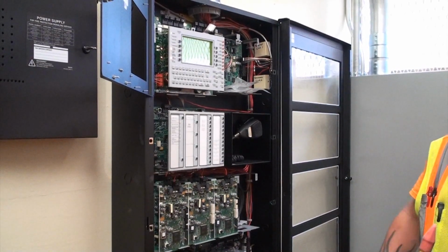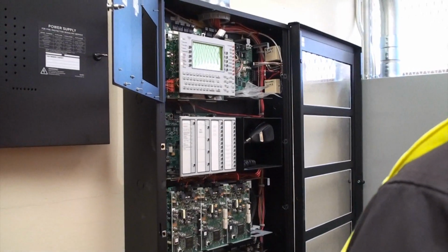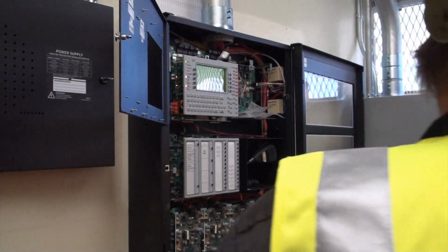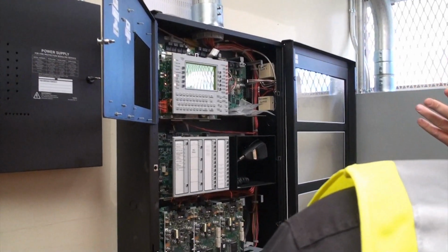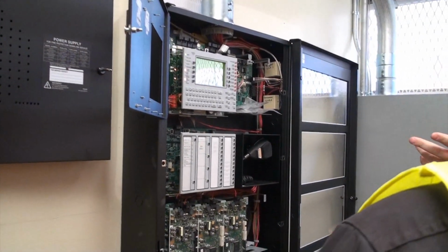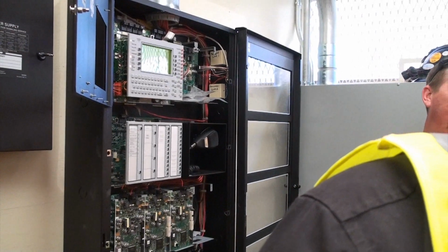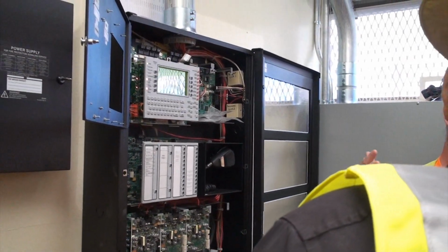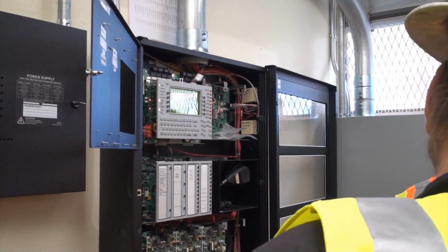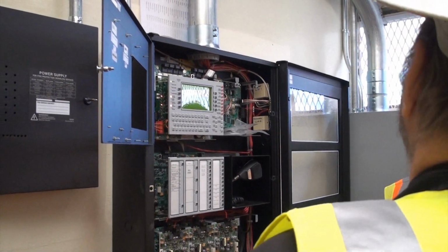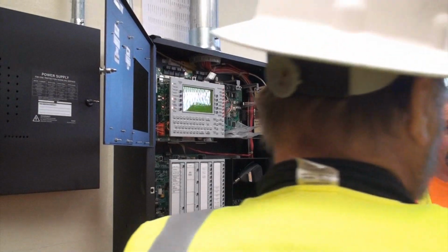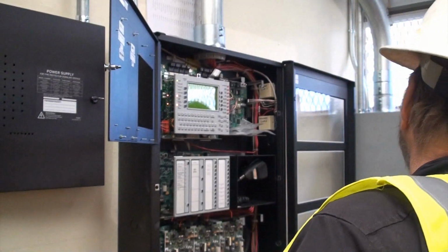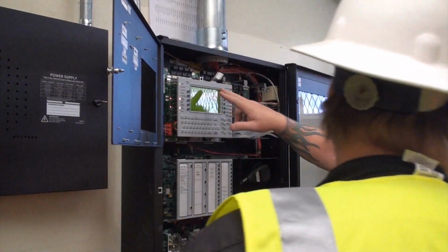When that one triggers remotely over there, it demonstrates the node. Will the node detail where it's found? Yeah, it'll say node 1, which is this one, building 200, second floor, smoke detector, this room, whatever the description is. Okay. And what happens when the old alarm trips? Say a 400 trips, what's it going to read over here? It'll say alarm existing panel.